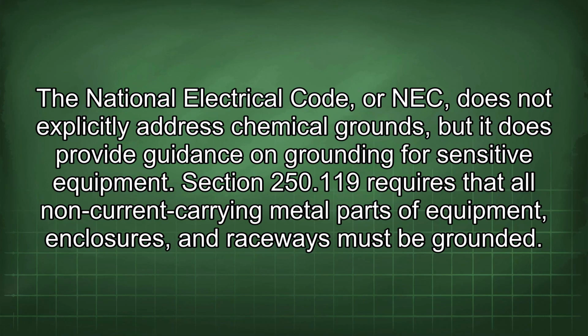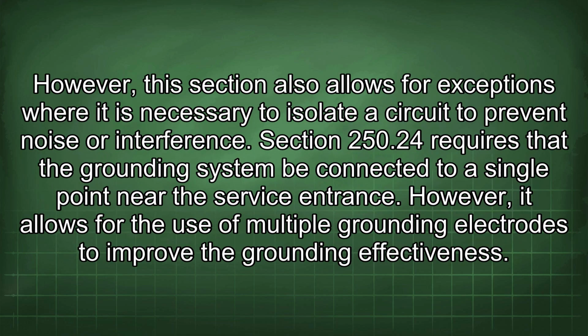The National Electrical Code, or NEC, does not explicitly address chemical grounds, but it does provide guidance on grounding for sensitive equipment. Section 250.119 requires that all non-current carrying metal parts of equipment, enclosures, and raceways must be grounded. However, this section also allows for exceptions where it is necessary to isolate a circuit to prevent noise or interference.